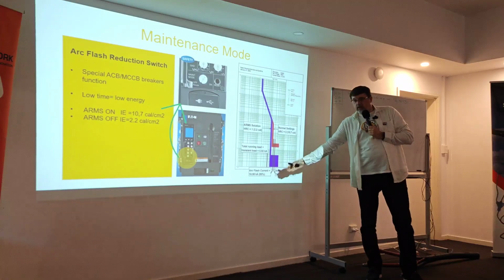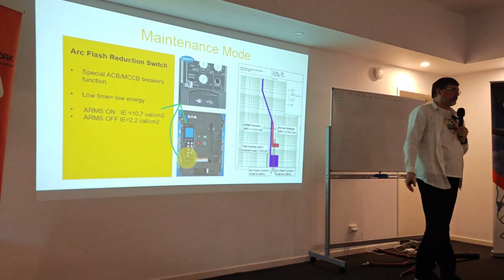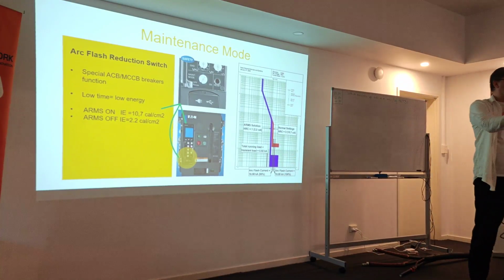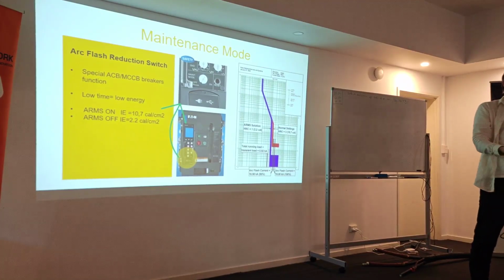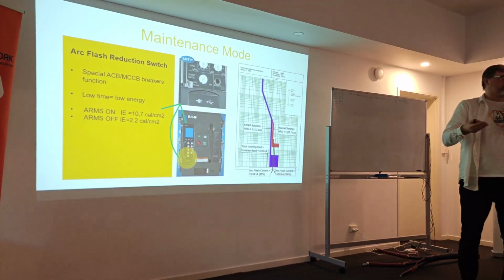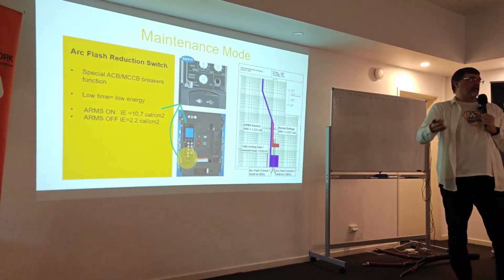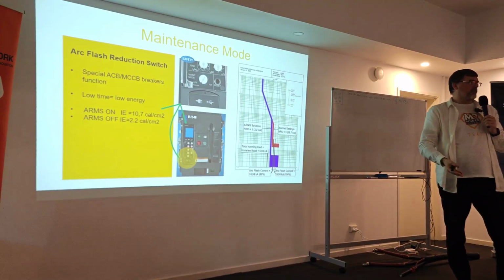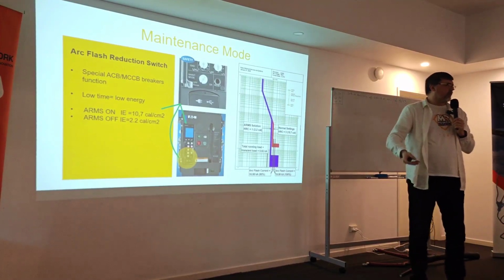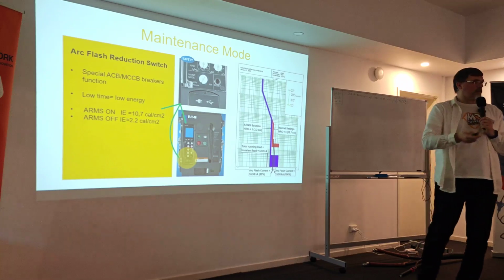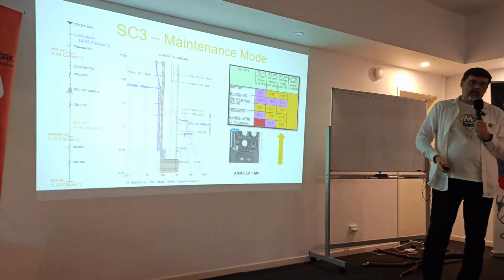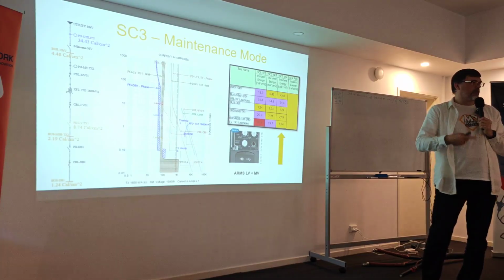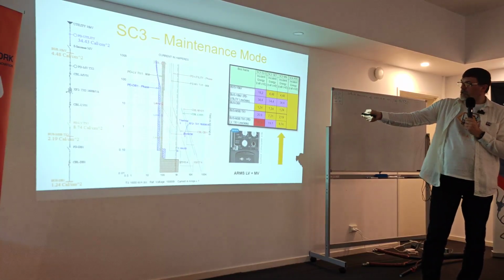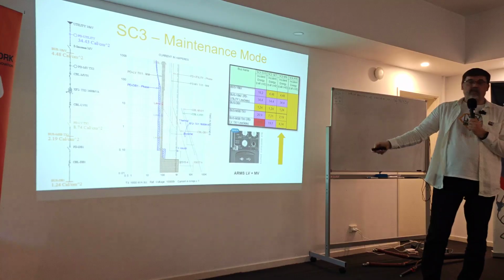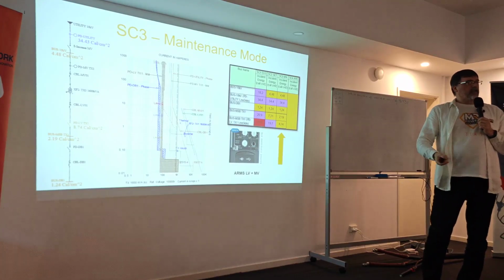It's just an override of the settings for the time that you are there, because at some point you are working. We want to drop the energy to a manageable level, and we, as a person, are more important than the equipment for a moment. And if something happens, the equipment will stop, yeah? So just for the next 1 hour or 2 hours, we reduce the trip and make it faster. But you don't want to keep it fast like this all the time, because it will be a problem for operation. So this technically looks like this. You can see it's not selective anymore from the downstream level, but it's fast.